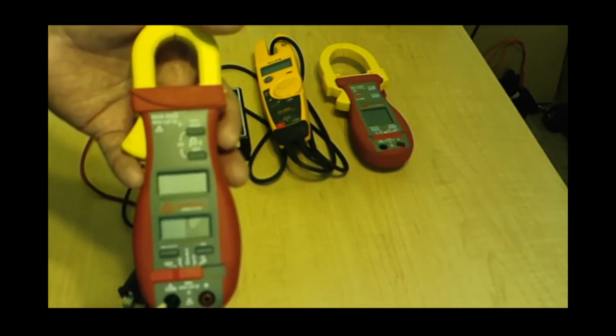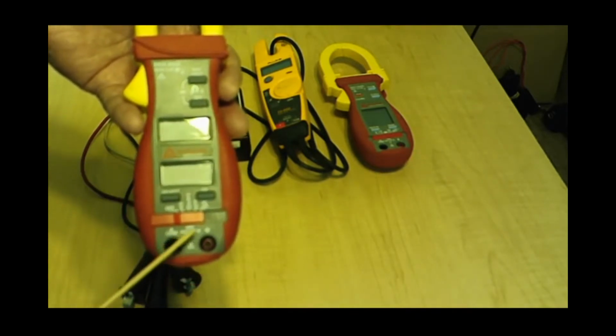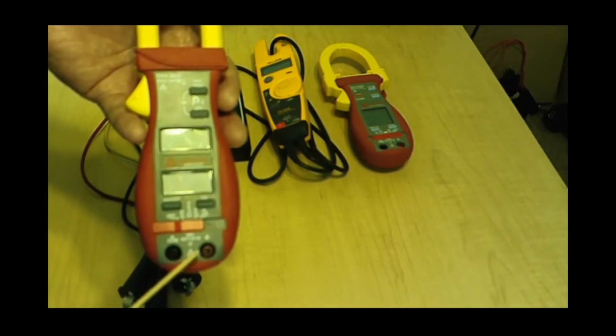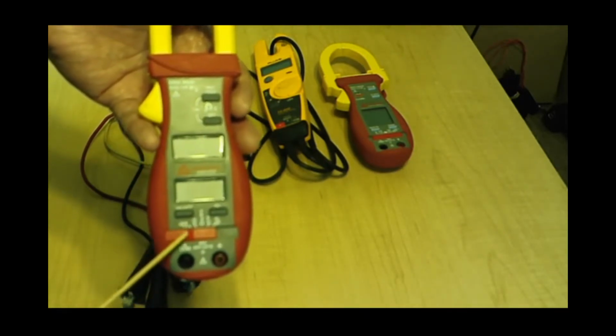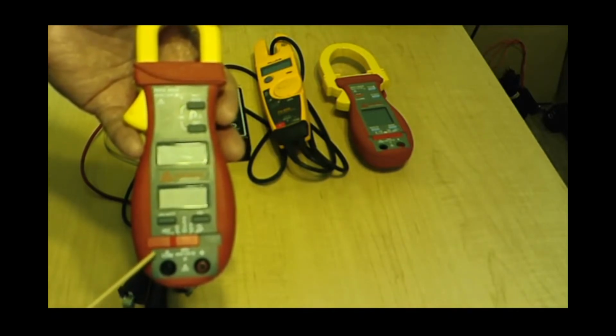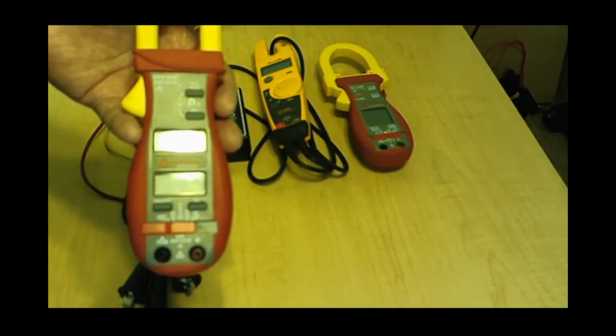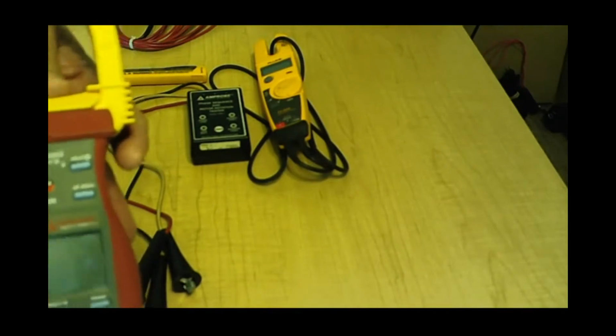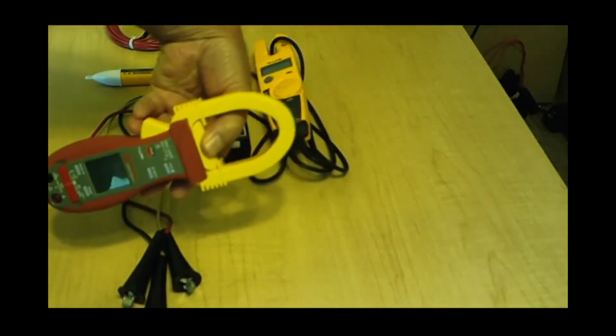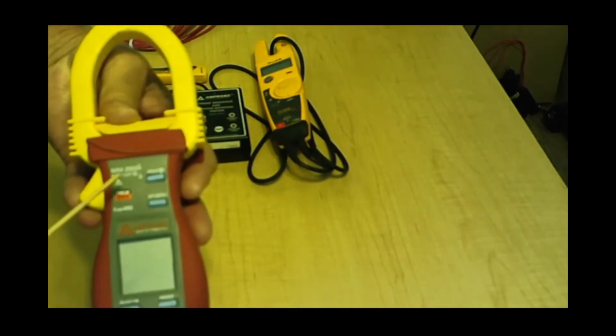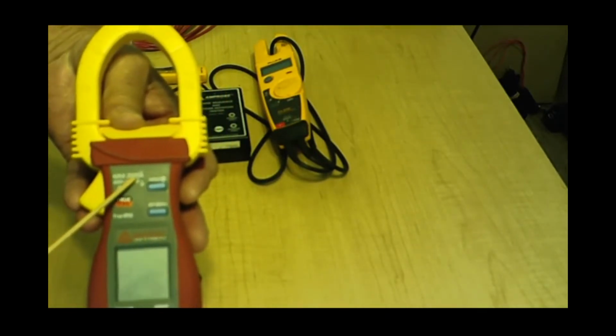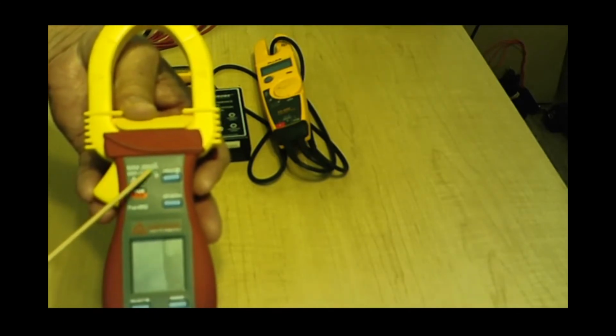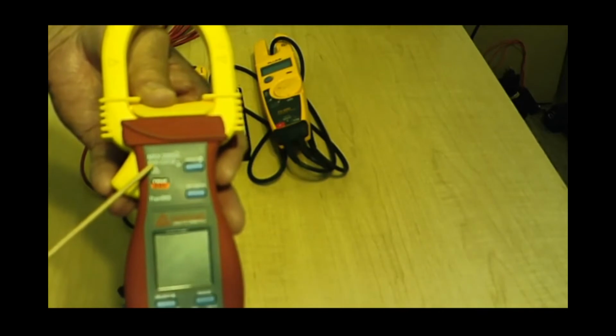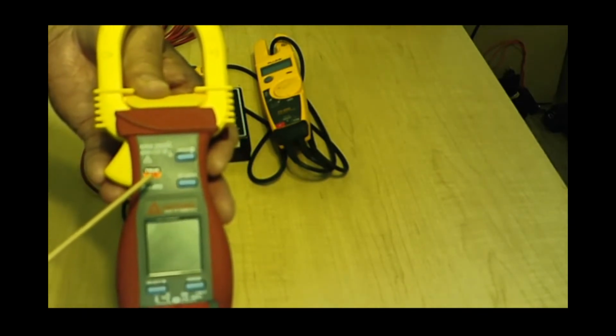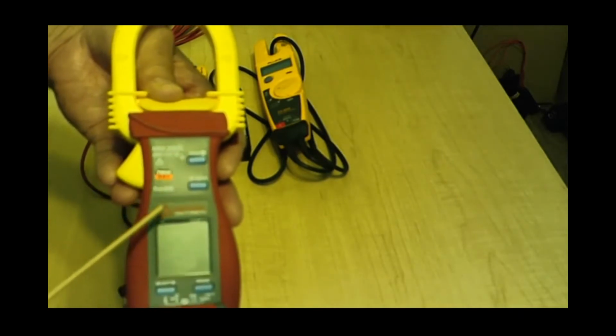We get into that. Now down here, the voltage rating on this meter is 600 volts maximum, Cat 3. Two terminals here for voltage. Indicator dial here dials into what I want to measure. So kind of a simple meter right there, very popular, but they do have a small screen, hard to read. Here's another version of that amp probe meter. This one is another clamp-on amp meter. This one has got a maximum of 2,000 amps. Category 3, 600 volts. So as long as I'm at 600 volts and less, I can measure up to 2,000 amps with this meter. And I can use it in category 3 locations.